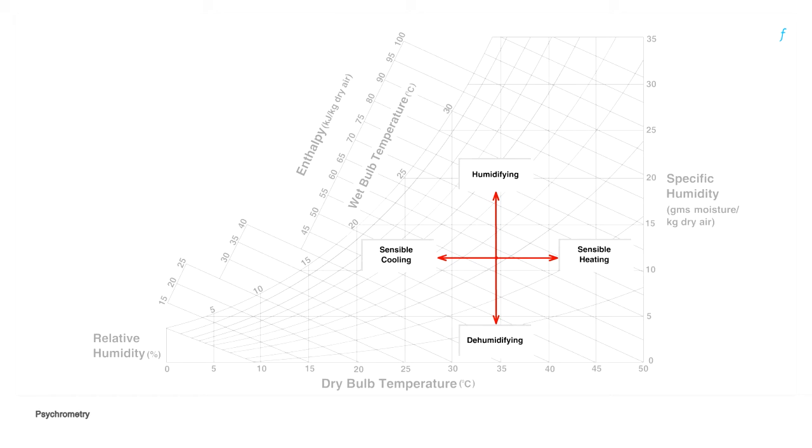Moving perpendicular to the wet bulb temperature lines would cause a combination of cooling and dehumidification or heating and humidification. Moving along the wet bulb temperature line downwards would be heating and dehumidification whereas upwards would be cooling and humidification, which is what happens during evaporative cooling.